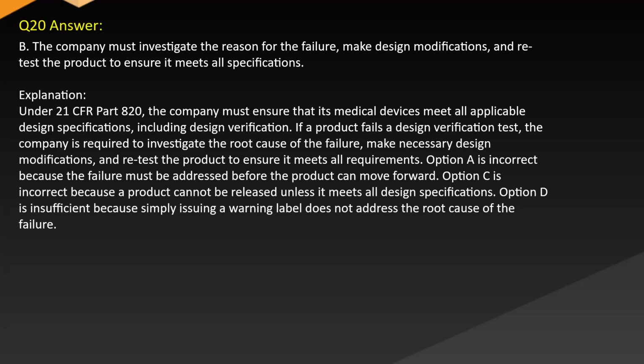If the product fails a design verification test, the company is required to investigate the root cause of the failure, make necessary design modifications, and retest the product to ensure it meets all requirements. Option A is incorrect because the failure must be addressed before the product can move forward. Option C is incorrect because a product cannot be released unless it meets all design specifications. Option D is insufficient because simply issuing a warning label does not address the root cause of the failure.